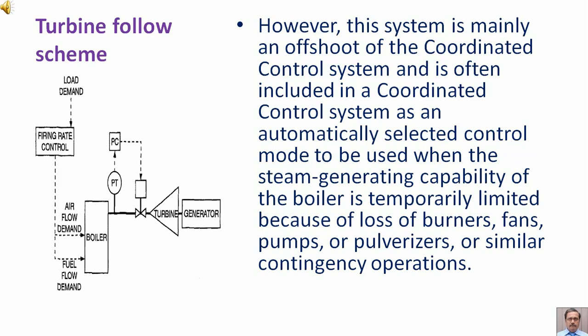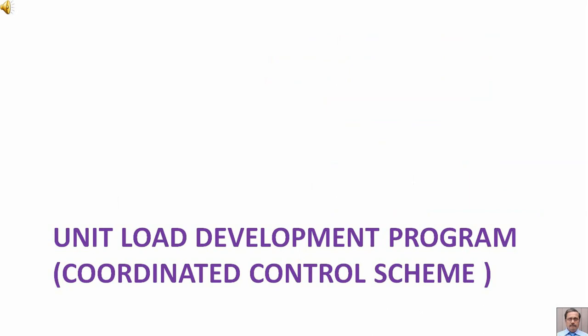However, this system is mainly an offshoot of the coordinated control system, and is often included in a coordinated control system as an automatically selected control mode, to be used when the steam generating capability of the boiler is temporarily limited because of loss of burners, fans, pumps, pulverizers, or similar contingency operations.